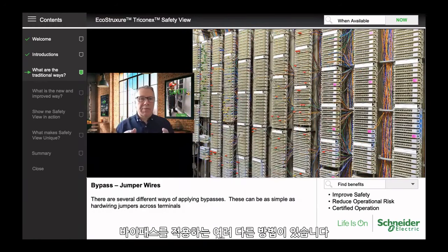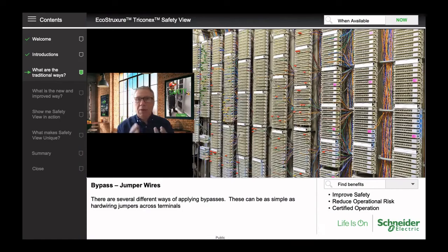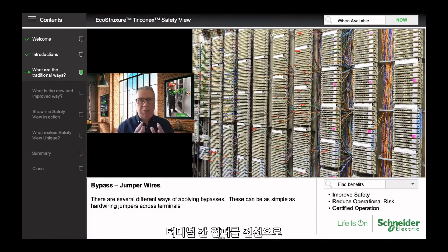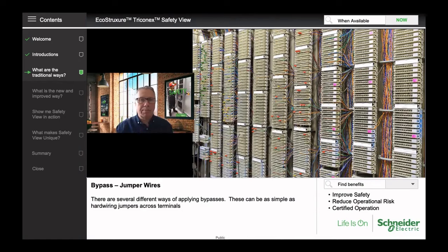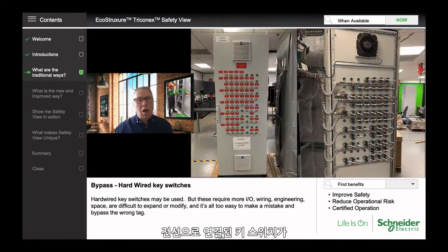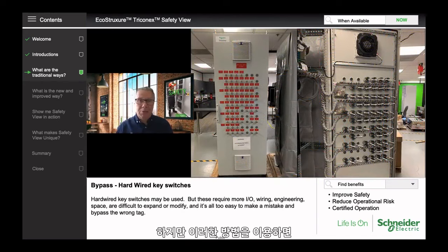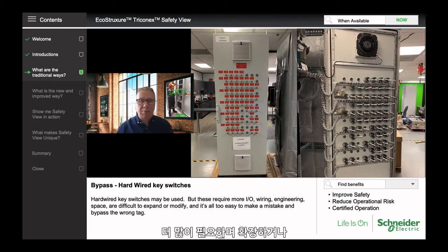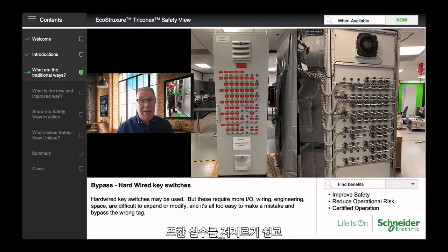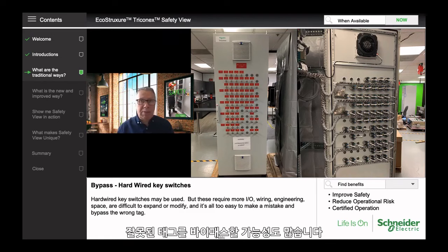There are several different ways of applying bypasses. These can be as simple as just hardwiring jumpers across terminals. Hardwired keyswitches may be used, but these require more I/O, wiring, engineering, and space. They're difficult to expand or modify, and it's all too easy to make a mistake and bypass the wrong tag.